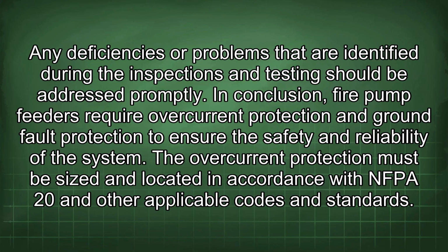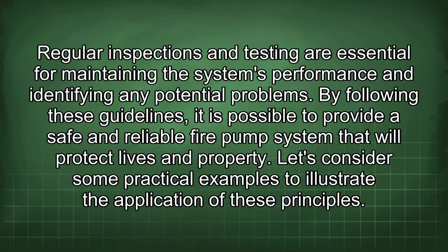In conclusion, fire pump feeders require overcurrent protection and ground fault protection to ensure the safety and reliability of the system. The overcurrent protection must be sized and located in accordance with NFPA 20 and other applicable codes and standards. Regular inspections and testing are essential for maintaining the system's performance and identifying any potential problems. By following these guidelines, it is possible to provide a safe and reliable fire pump system that will protect lives and property. Let's consider some practical examples to illustrate the application of these principles.